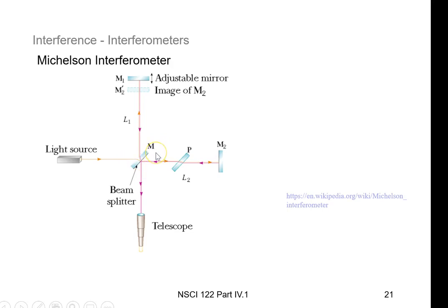The beam splitter is just a piece of glass, and on one side of it, they will have deposited a thin layer of metal. Now, the layer of metal is so thin that not all the light that hits the metal is going to reflect. If they wanted to make a conventional mirror, they would make that layer of metal thick enough so that none of the light would get through. But by varying the thickness of that metal, they can make whatever percentage of the light reflect that they want, and the remaining percentage will go through.